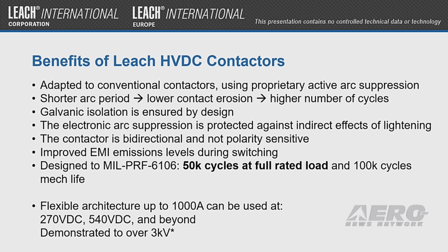We're very good at building contactors. We've been doing it for decades, and we have our proprietary arc suppression added to that. So we can shorten the arc, reduce the contact erosion, allow for a higher number of cycles, and we still maintain galvanic isolation on that product.